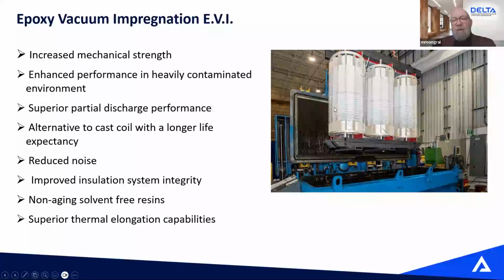So the picture that you see there, that's in our power section, that transformer is probably a 5 MVA, 25 kV class. So we take the entire core and coil, put that in the chamber, we close the lid, and while we vacuum the chamber, we inject epoxy, we fill the tank with epoxy, so the epoxy will go everywhere, all the windings, all the layers. We even seal the core and the core structure with epoxy.